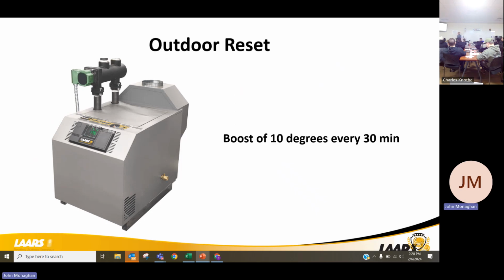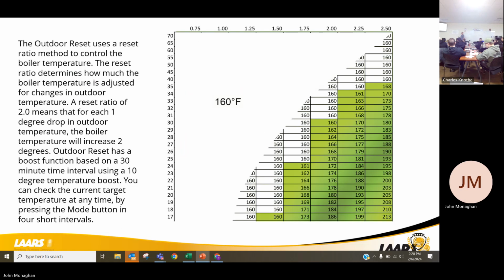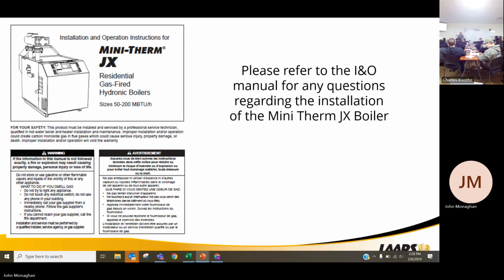So again, 10 degrees every 30 minutes if it's not keeping up with this temperature. If we got too aggressive on our reset curve, or that sensor's not sensing correctly, the boiler is running for 30 minutes, it's going to increase temperature by 10 degrees every 30 minutes till it satisfies. There goes another shot of the curve. You can have your settings 1.25, 1.5 to adjust whatever your outdoor sensor may be. And there's a good chart outlining it inside the I&O manual. There we go, referring to the I&O manual. Any questions on the JX?